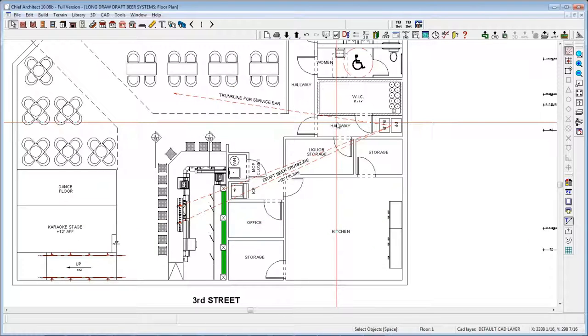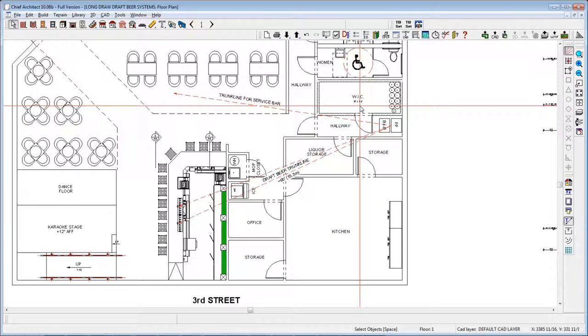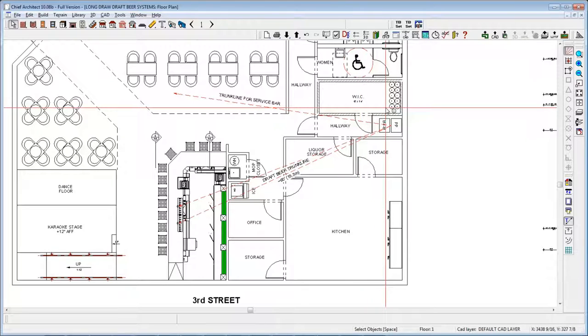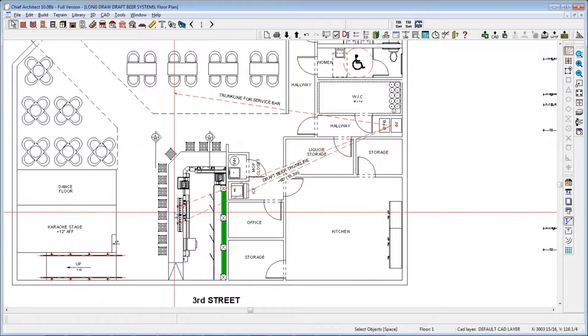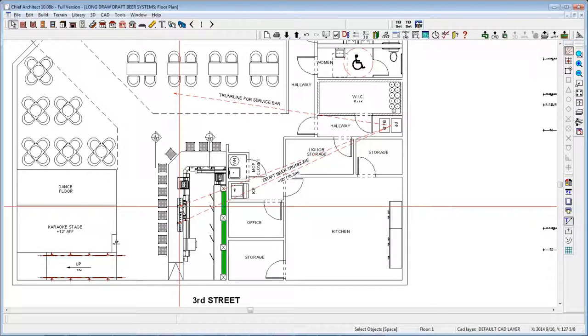The fundamental challenge of glycol draft beer systems is to transport the beer from the walk-in cooler over here, whose temperature is 36 to 38 degrees Fahrenheit, over a significant distance, and dispense the beer over here at this tower at 36 to 38 degrees Fahrenheit. This is mandated by the brewers and has been deemed to be the ideal temperature range for draft beer to maintain its intended characteristics. Now, as the beer travels along its journey, it tends to increase in temperature due to the gas that's pushing it and the resulting drag of the plastic product lines that resist. Therefore, heat accumulates inside the product lines.